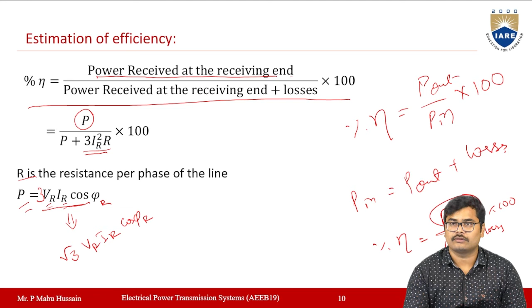Let us see one simple problem so that you can understand how to estimate the efficiency and regulation for a short transmission line. Read the problem: a single phase 50 Hz generator supplies an inductive load of 5000 kilowatts at a power factor of 0.707 lagging by means of an overhead transmission line 20 kilometers long, and the line resistance and inductance are 0.0195 ohms and 0.63 millihenries per kilometer. Observe that these are for 1 kilometer.